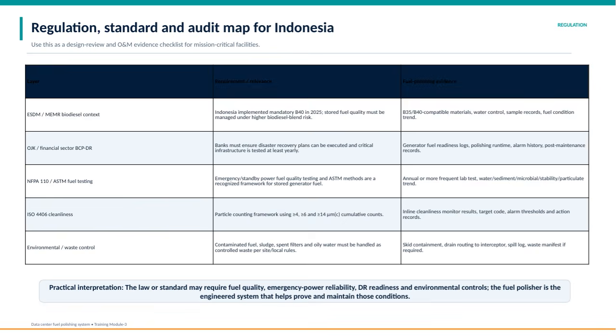Next, the financial sector, particularly banks regulated by OJK, must have disaster recovery plans in place. These plans require annual testing of critical infrastructure, including generators. Fuel readiness is monitored through detailed logs, records of fuel polishing runtime, alarm histories, and post-maintenance documentation to ensure reliability.